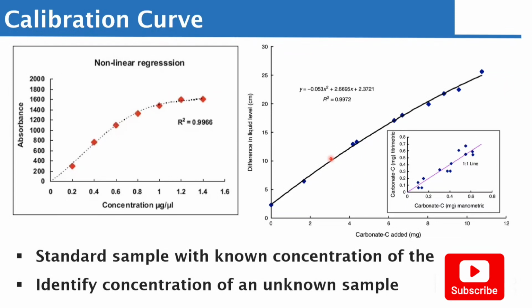I'm trying to explain that the calibration you are talking about is a curve. And that curve generates targeted ranges in which the analyzer measures. Does that make sense? It means that anything outside the ranges, the analyzer cannot measure. I hope I've been able to explain this. Now, let me explain why sometimes we say, if my QC failed, I'm going to redo the calibration.